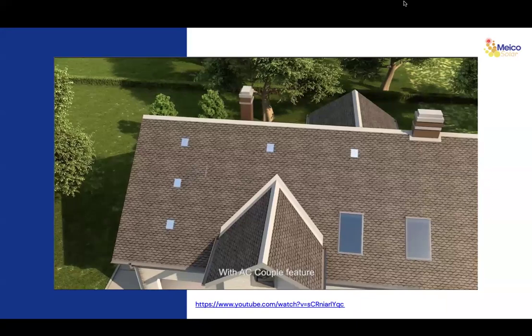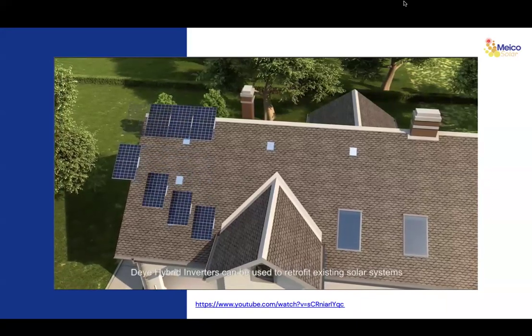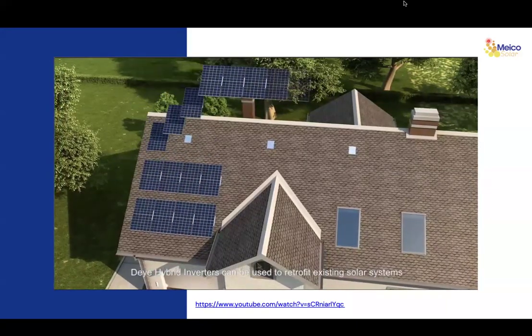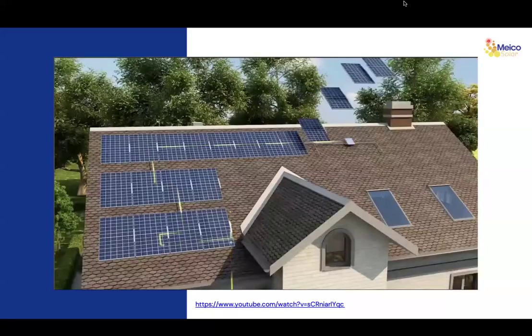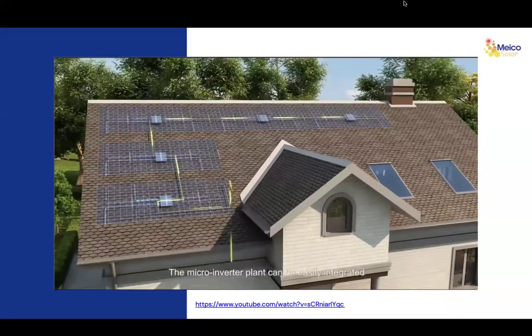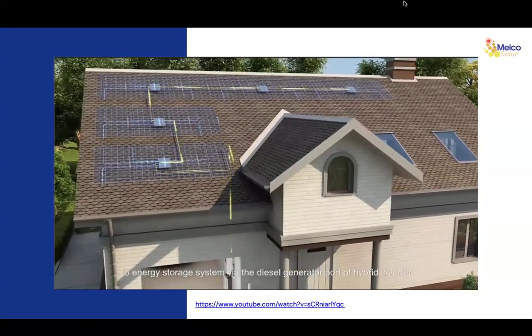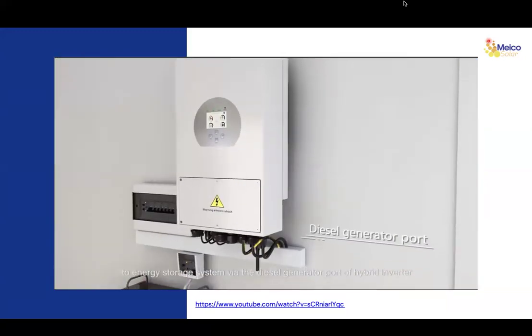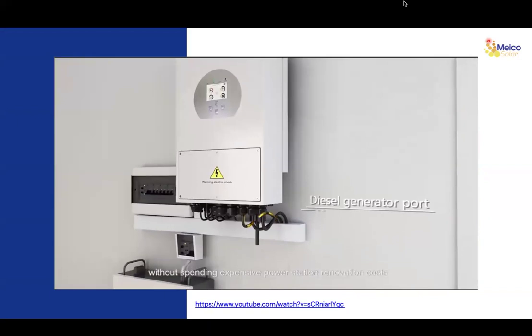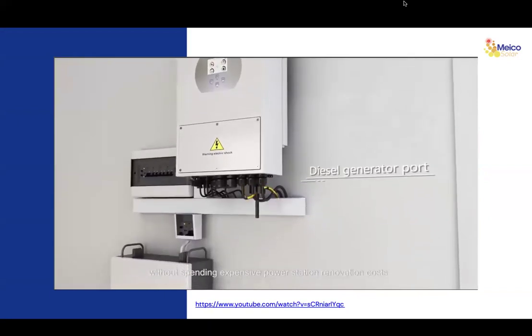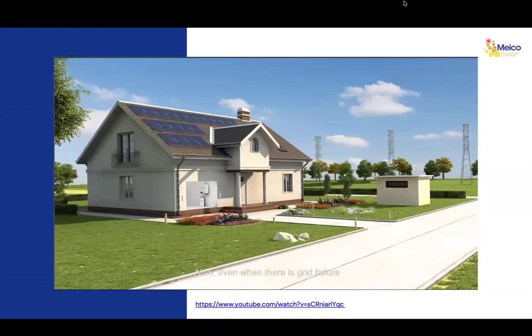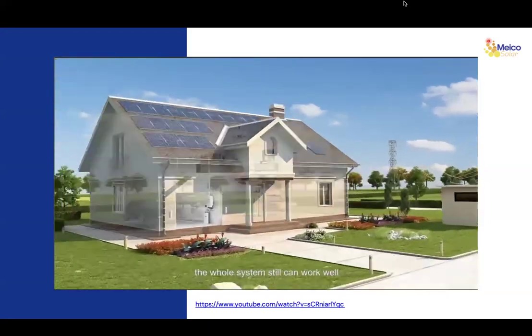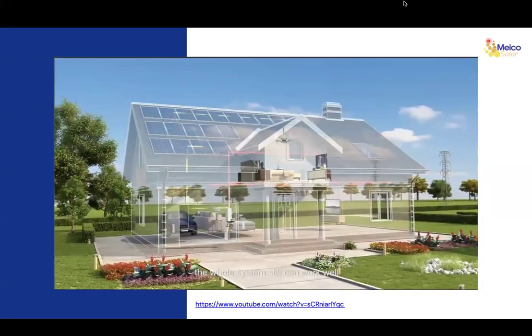With the AC couple feature, Deye Hybrid Inverters can be used to retrofit existing solar systems. The microinverter plant can be easily integrated into the energy storage system via the diesel generator port of the hybrid inverter without spending expensive power station renovation costs. Also, even when there is grid failure, the whole system still can work well.